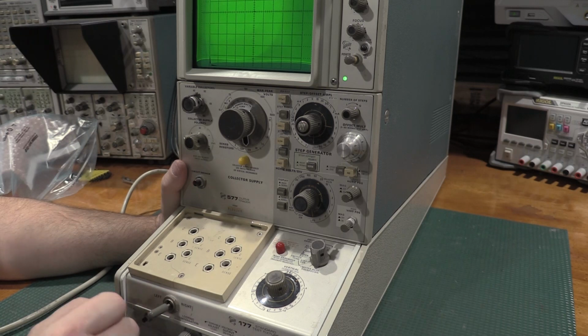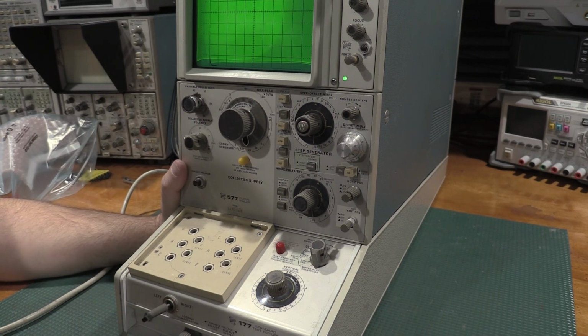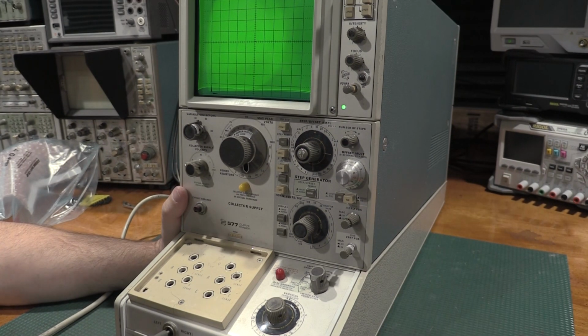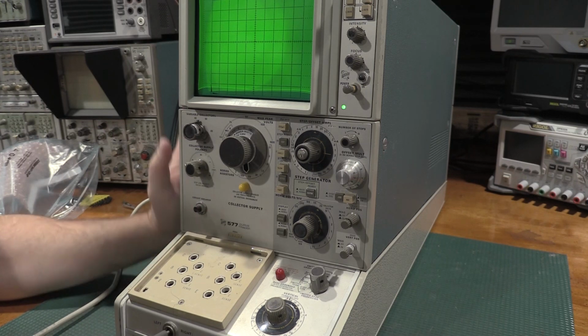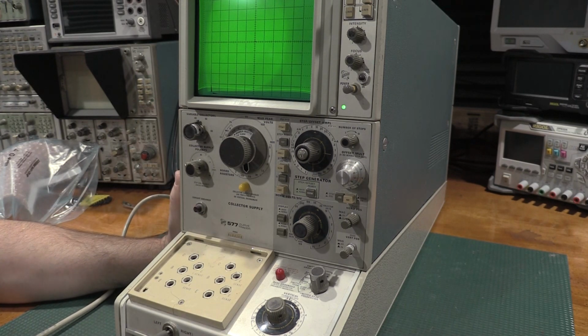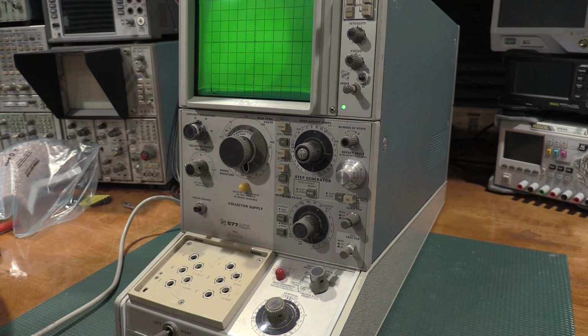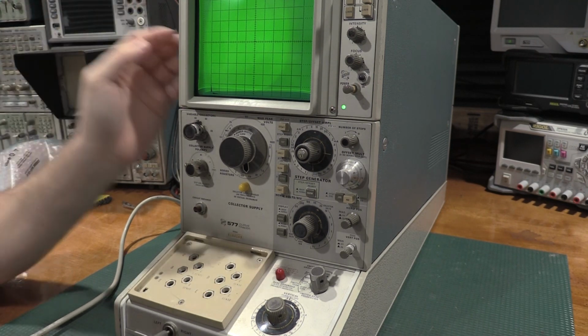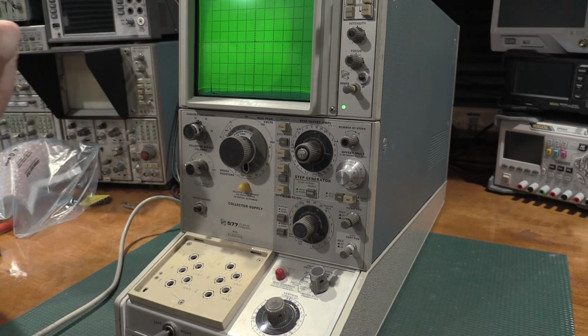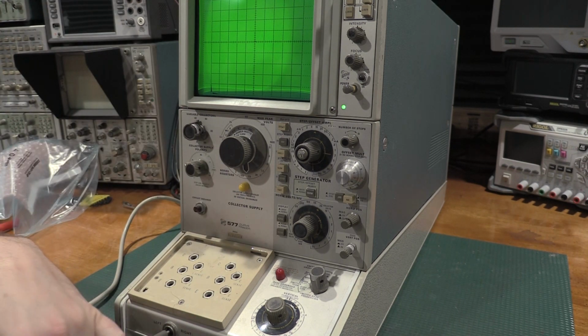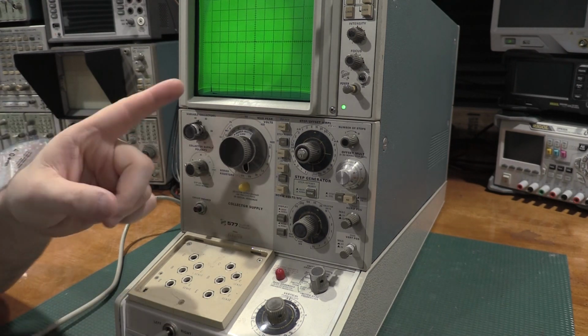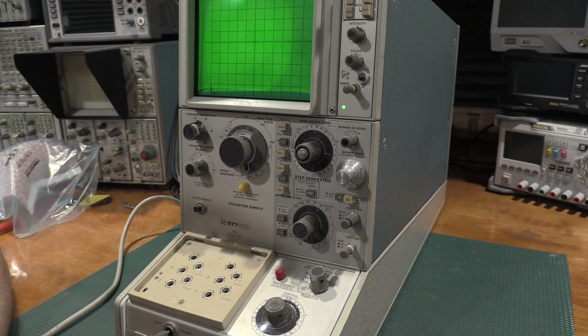You can buy a new center and get another switch if it's something that you would like to look for. If you're doing an alignment on these and you're really struggling to do an alignment on a 576, there is a separate alignment procedure for the 177. If you haven't done that, do that one and see if the alignment will converge on the 176 or the 576. I ran into that and found that one out the hard way, was because some of the balance points in the 177 were off, and that was causing my alignment on the CRT to not go well.